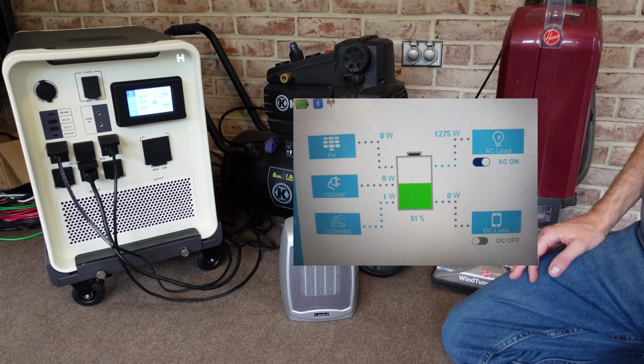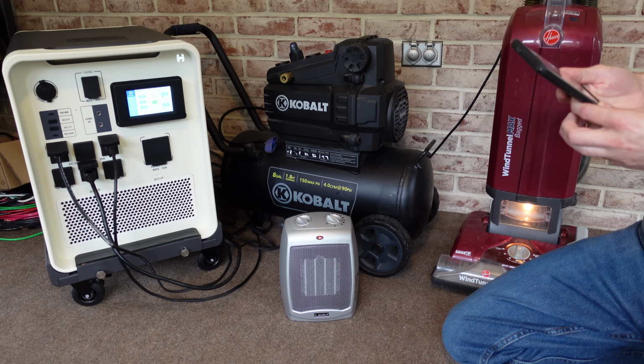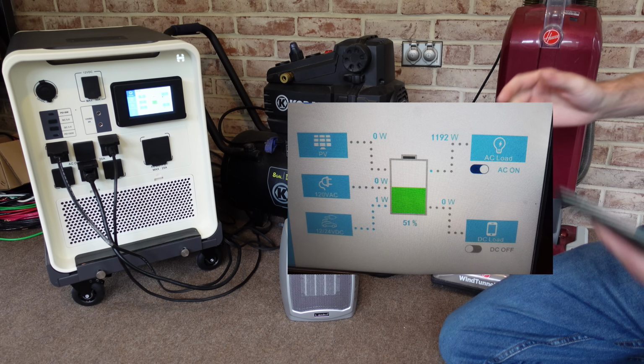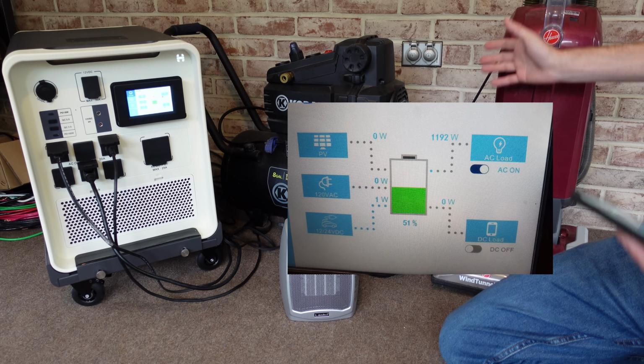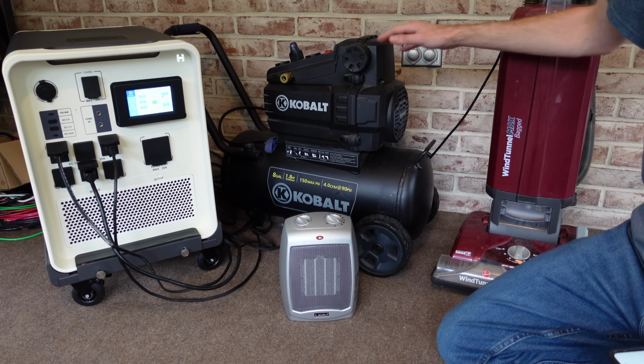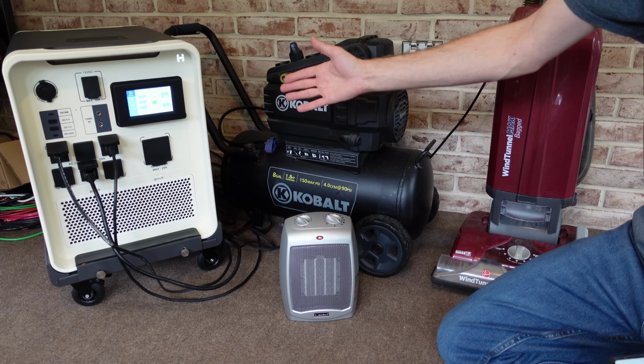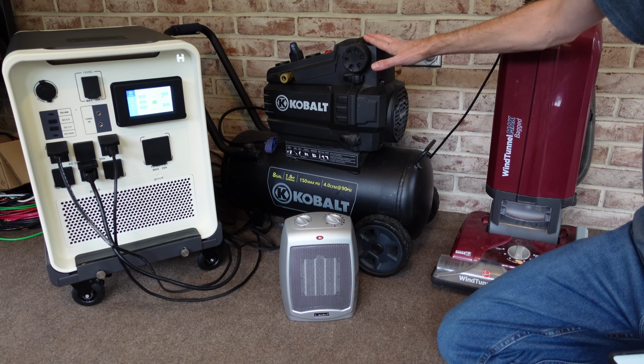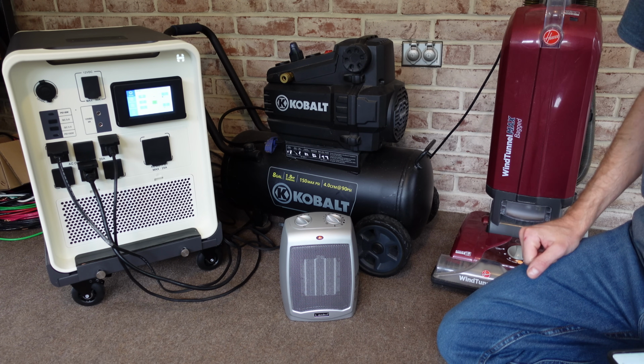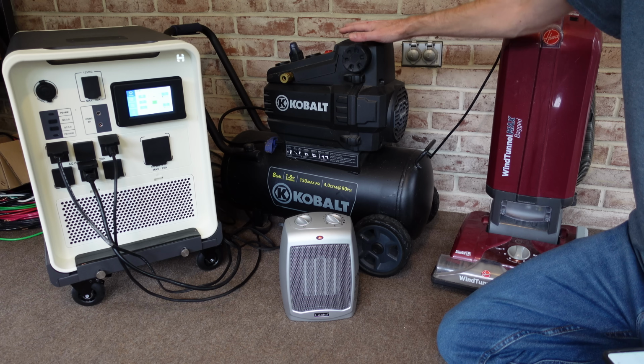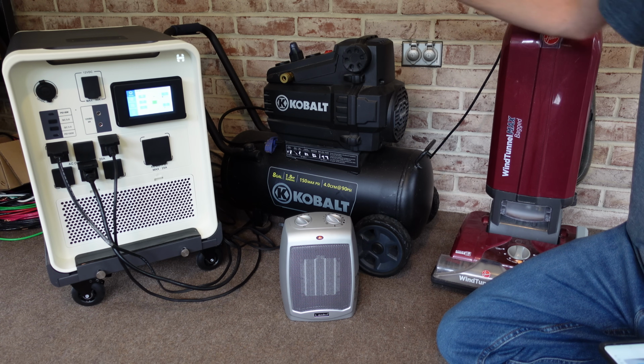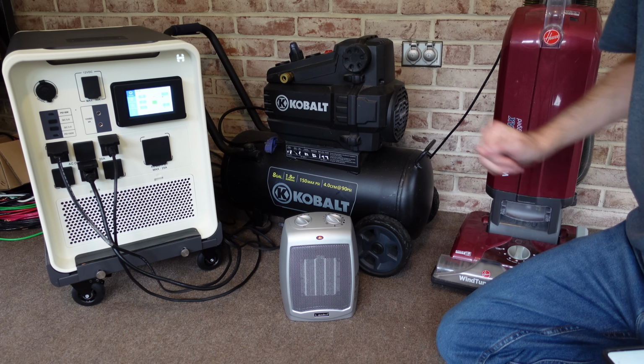And that measured approximately 1275 watts. And the vacuum cleaner measured approximately 1200 watts. Both of these combined are still below the 3000 that this is rated for, but again, with inductive loads, it's always the initial startup current. So because this is the heavier of the two, I'm going to start the vacuum cleaner and then start the air compressor and see if this shuts down.